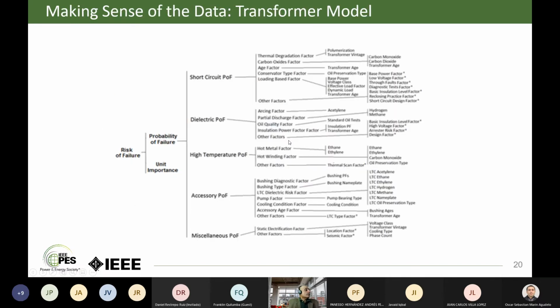So now, how do you make sense of all of that data? We want to create a risk of failure, defined as probability of failure and importance. The importance can be calculated differently because it involves financial components — let's leave that for now. Let's just look at the probability of failure. Now we look at how many ways the transformer can fail: short circuit, dielectric, high temperature, accessories, and miscellaneous.